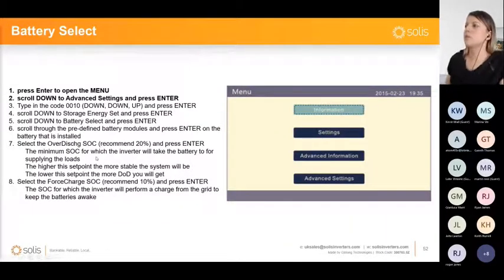Okay, so the menu is quite simple. You have the information, settings, advanced information, and advanced settings. For information and settings, you don't need any passwords to access them. But for advanced information, where, for example, you can see historical alarms, or for advanced settings, where you're going to set the storage modes and time charging modes, battery selections, these require a password, which is always 0010. This is down, down, up, enter. You can find this in the manual as well.